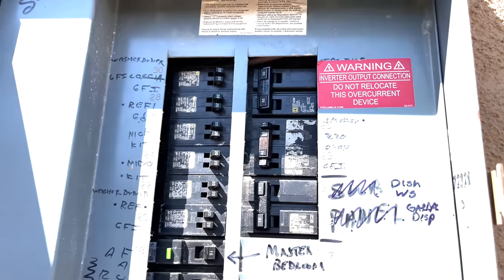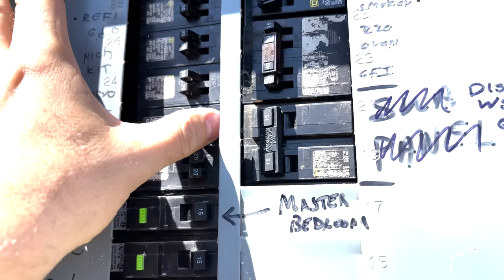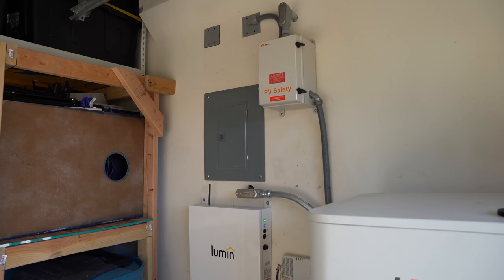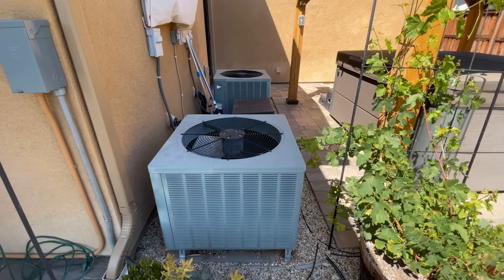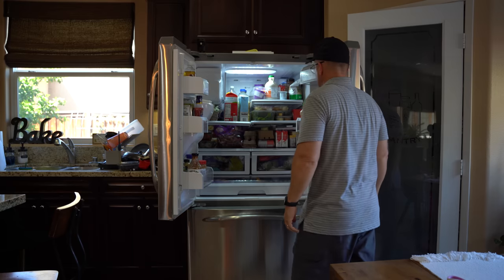Let's run this through a test showcasing these features. I'm going to show you an example where I flip off the circuit breakers to the house, so the house is now disconnected from the grid. Looking at the Lumin screen, we see that it's charging the batteries from solar and power is going into the house. What ultimately gets powered in the house is determined by the lines we set up on our sub panel connected to the smart panel. You can power more power-intensive devices such as your air conditioner with this system, but I personally decided to only power critical devices to conserve power for what I thought is most important. Let's take a look in the house to see what's actually still running after I shut off the power coming from the grid.